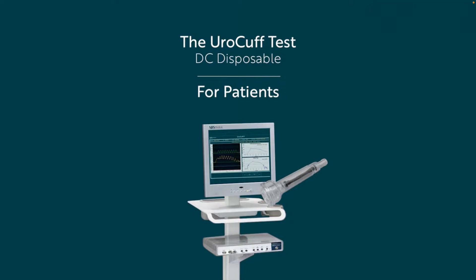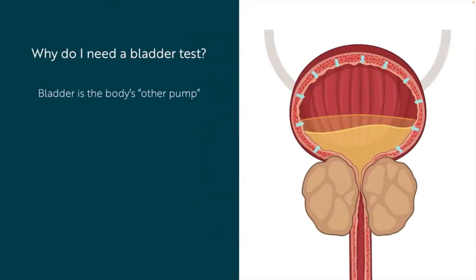The bladder is the body's other pump. It is responsible for the storage and emptying of urine. In order to properly diagnose your urinary tract issues, the doctor needs information about your bladder performance. Bladder function can be assessed by evaluating how much it holds, how hard it squeezes to get urine out, and how fast urine actually comes out, amongst other things. A healthy bladder holds urine well and doesn't have to squeeze hard to get urine out quickly. Over time that pattern can change, and that's what the UroCuff evaluates.